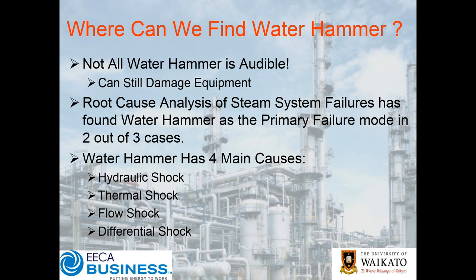There are also some less-than-ideal heat exchanger designs you'd want to consider — and perhaps we might do a webinar on that topic. Send us some feedback if that's an area of interest. What we want to get to today is the four main causes of water hammer: hydraulic shock, thermal shock, flow shock, and differential shock. The common element is the 'shock' term — what we're really talking about is that water hammer is caused by some sort of shock or impulse in the system. Something's changing.